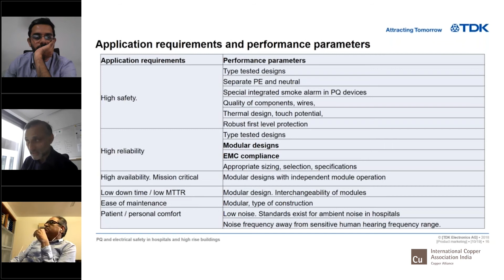And this is something very key about hospitals. You talk about all electrical equipment, and in this particular case, we found out that the patients were complaining about the high noise coming from the DB room. We know that all electrical equipment makes noise. A transformer makes a hum because of magnetostriction. Even capacitors make a noise. Active filters make a lot of noise. So now there are standards available in the building code for hospitals. All the UK hospitals use this, where the ambient noise should be less than, let's say, 55 dB, and you cannot meet the hospital noise standards unless even the electrical equipment there complies with the noise standards.